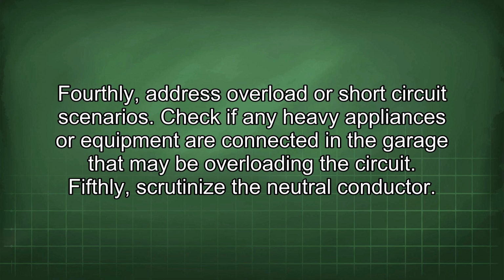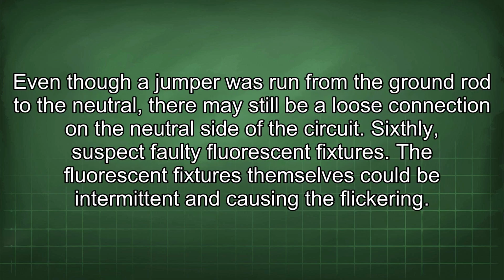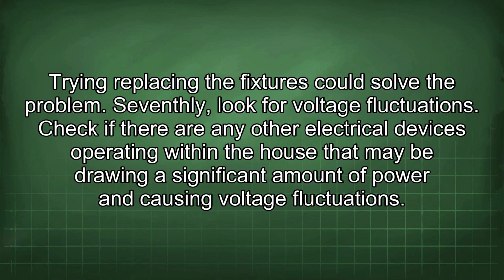Fifthly, scrutinize the neutral conductor. Even though a jumper was run from the ground rod to the neutral, there may still be a loose connection on the neutral side of the circuit. Sixthly, suspect faulty fluorescent fixtures. The fluorescent fixtures themselves could be intermittent and causing the flickering. Try replacing the fixtures; it could solve the problem.